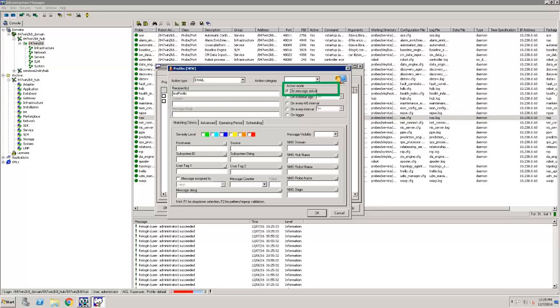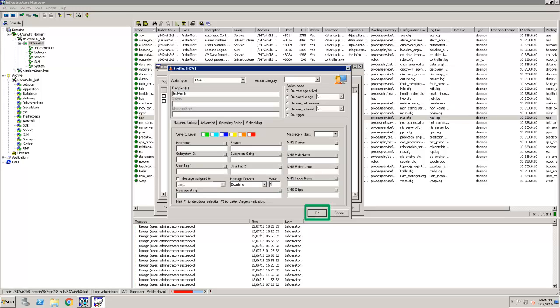I then change the Action Mode to On Message Arrival. Next, I change the Message Counter to Equals with a value of 1. This ensures that the user only receives an email the first time an alarm occurs.